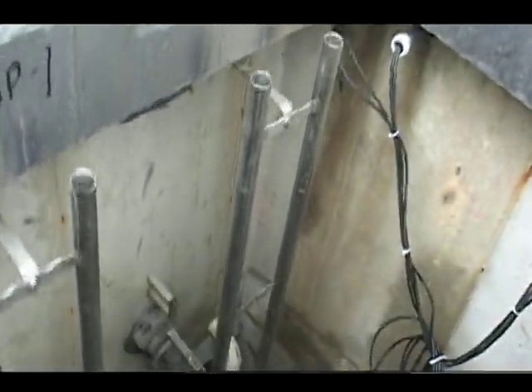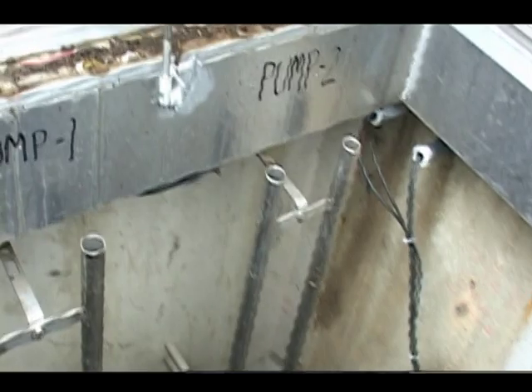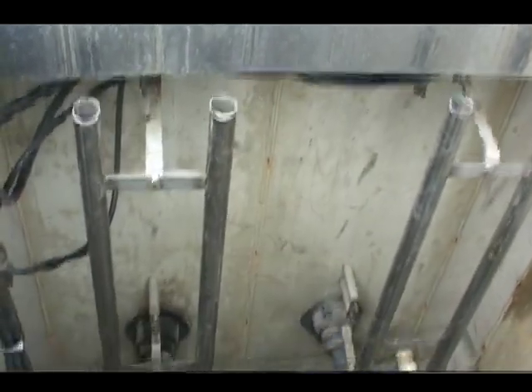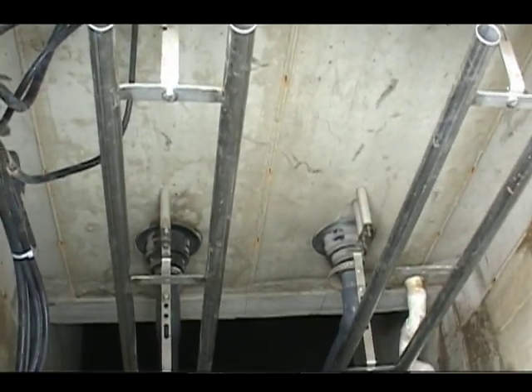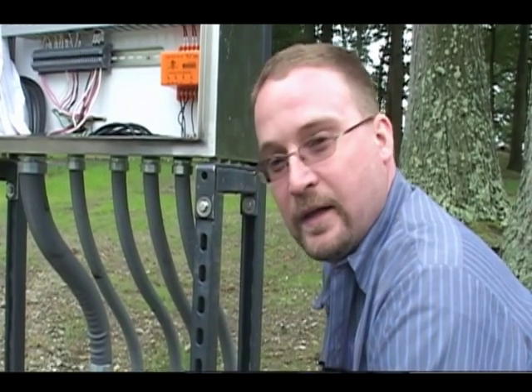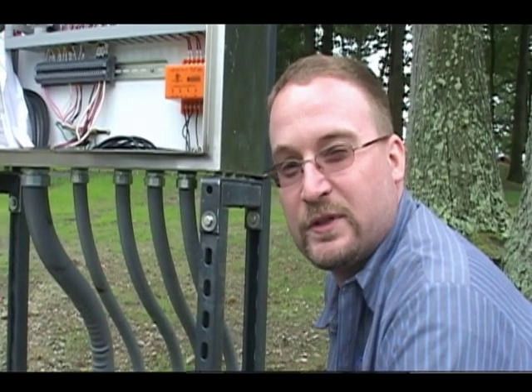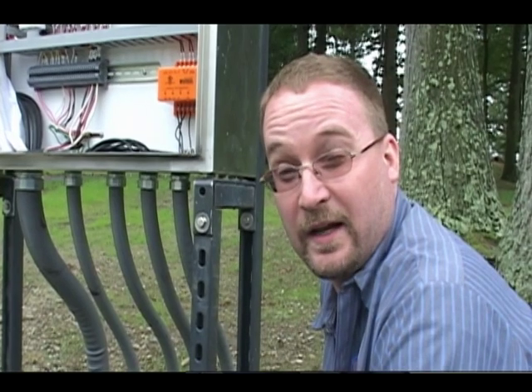Hi, my name's Steve from Mechanical Pump, here to talk to you about your Hydromatic explosion-proof grinder pumps. If you look down here, you'll see we got two horsepower explosion-proof grinder pumps set up on a TOPS rail system for easy removal. Our grinder pumps are set up with a dual cutter system consisting of a stationary cutter and a coaxial cutter, both of which are reversible, and the explosion-proof connection at the top, which has the double epoxy electrical conduits.